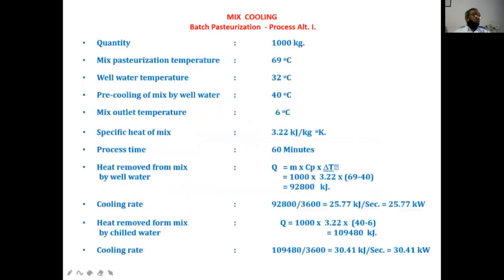Let me consider the cooling load. We want to make 1,000 liters of mix, pasteurization temperature 69 degrees centigrade, well water temperature 32 degrees centigrade, pre-cooling of mix by the well water to 40 degrees centigrade, and mix outlet temperature 6 degrees centigrade. These are the data available from the equipment design. Now we want to calculate what the cooling load is.